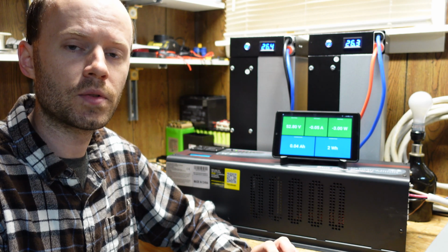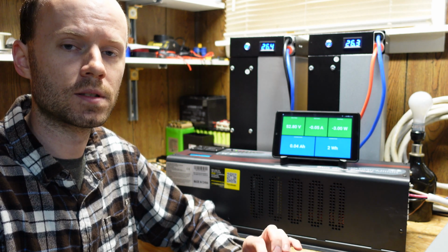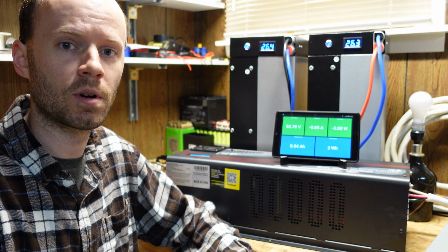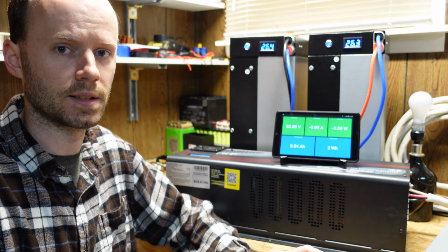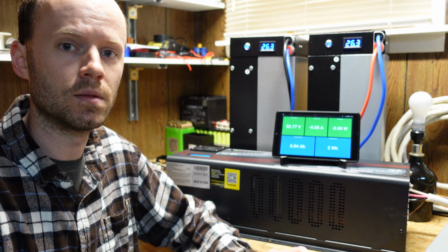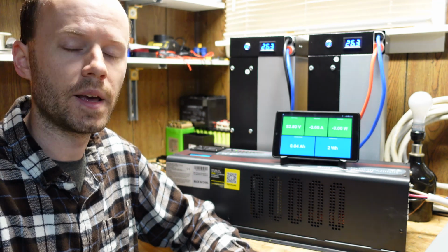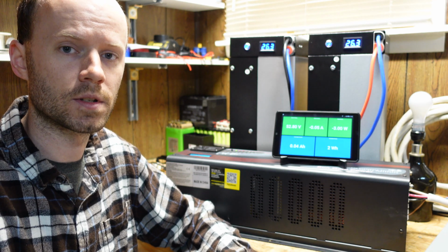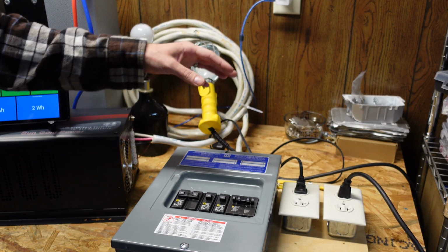Right there. So every 3 seconds, it sends a small pulse of electricity through the transformer of approximately 250 milliseconds. And it uses that to detect loads that are connected to the output of the inverter. And when it detects load, it will start up the inverter and turn on the normal output. So we can demonstrate that over here.